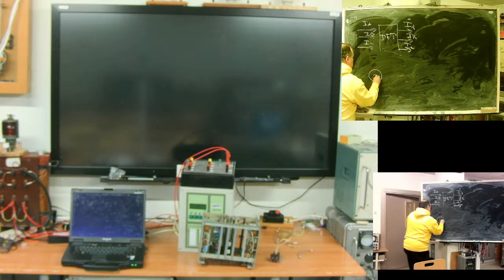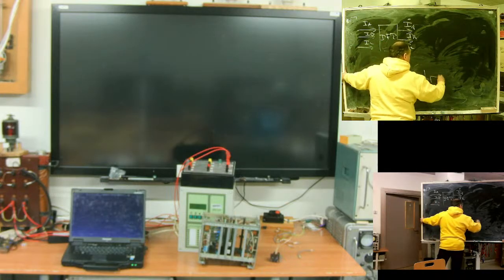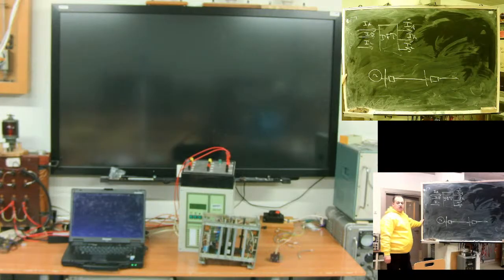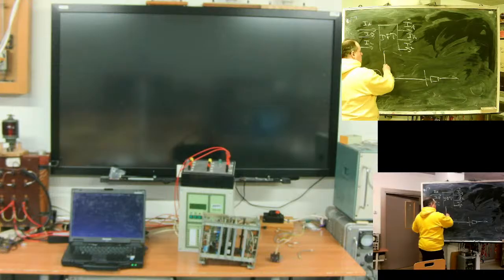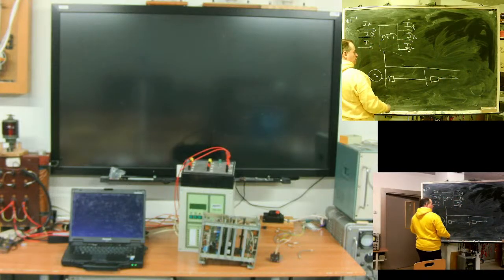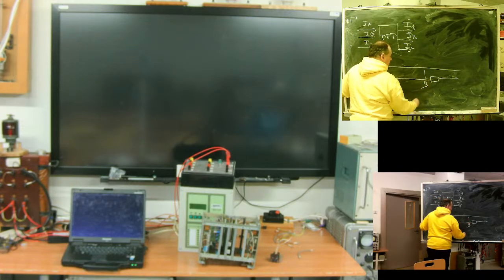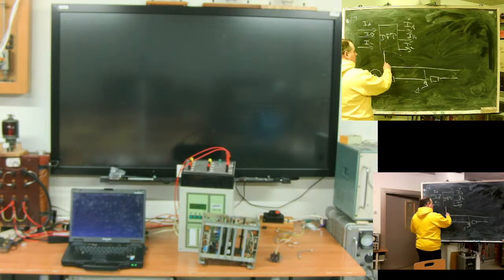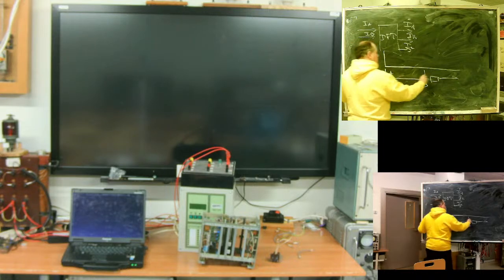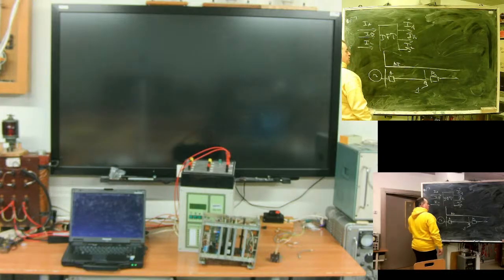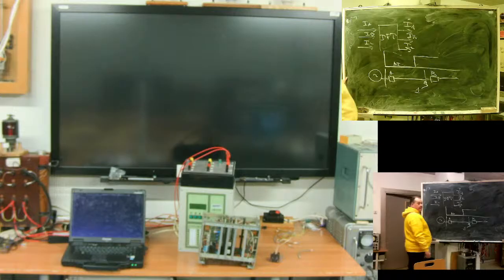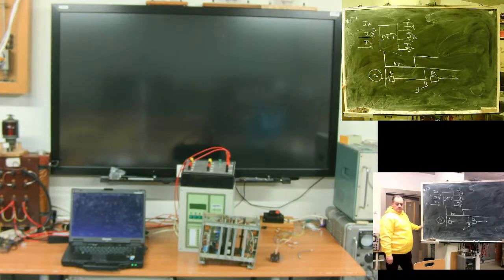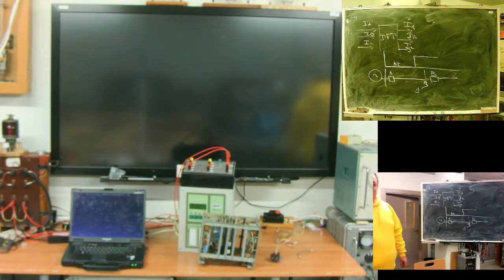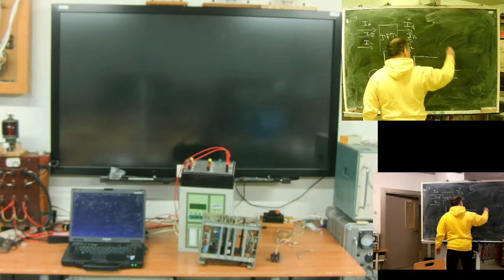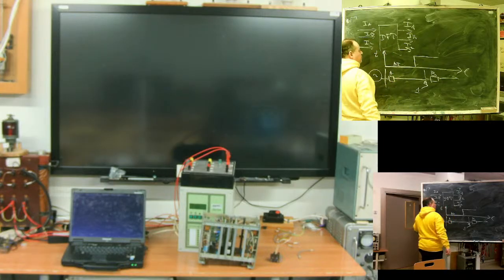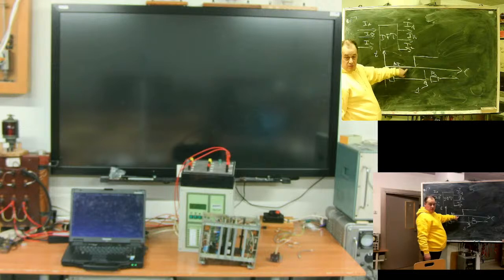Let's say you have a source, your line, and an adjacent line. What will be the structure of your overcurrent protection? Here, fault number 1. Instant zone, let's say this is A, this is B, so this will be A1. What will be the trip current for the instant zone? Power system protection course. Length. This is time of operation. Trip current for this primary zone.